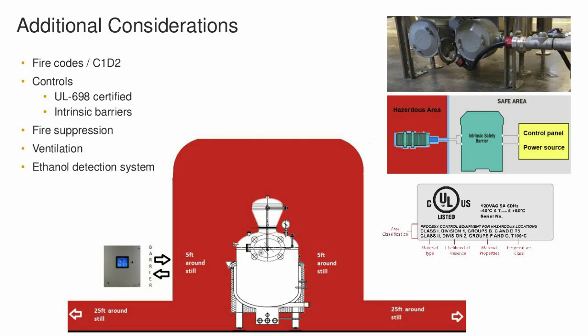C1D2 is what that's called. C1D2 is what the codes refer to as the classification of how explosive an environment is. So there's Class 1 Div 1, which is the most explosive. And what that means is that under regular operations, there will be explosive vapors in the air. That's not the case here. You're going to have vapors if something goes wrong, because the ethanol will actually vaporize at higher temperatures, and all those higher temperatures are happening within the still, and everything is a closed unit. But let's just say you have a leak in maybe a CIP arm, or like I said, your chiller shuts down unexpectedly, then you could have vapors that come out, and that's what the C1D2 is: you're only going to have vapors in the event that something goes wrong. That's the simple way to put it.